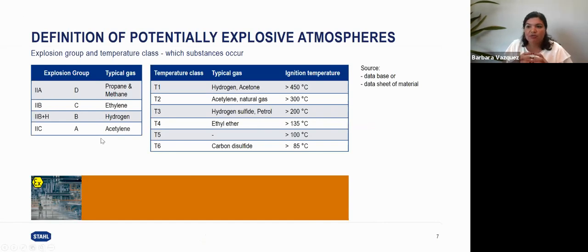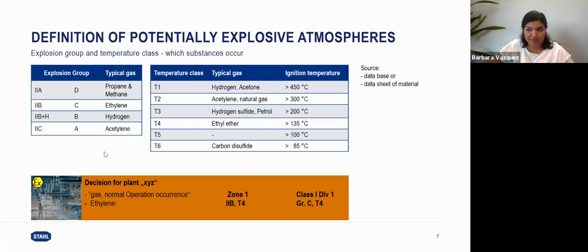So the area needs to be classified, also covering the group of gases and the T rating. This is very important information when we want to define the equipment we're going to install in that area. So we have a different group of gases and we have the different T ratings. So the proper classification will be something like American Zone 1 IIB T4 or Class I Div.1 Group C T4. So we need the entire part number. And a little bit later, we'll see some examples where that group of gas is really relevant when we're trying to, again, define the equipment that we need to use.